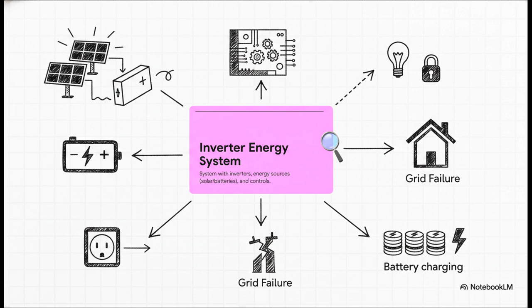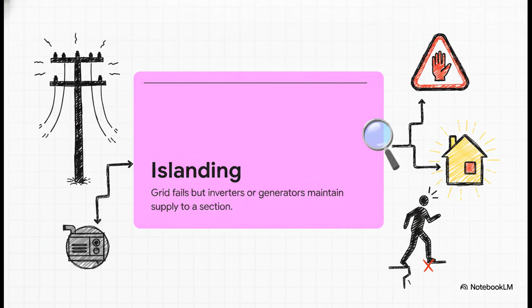Which brings us to a really critical concept: islanding. Islanding is essentially a situation where the grid supply fails, but an inverter or generator keeps pumping electricity to a section of the installation. Preventing these unintentional islands of power is an absolute key to maintaining your safety. If an inverter doesn't automatically disconnect during an outage like it's supposed to, you could be walking right into a live zone you thought was totally dead. No way you want to risk that.